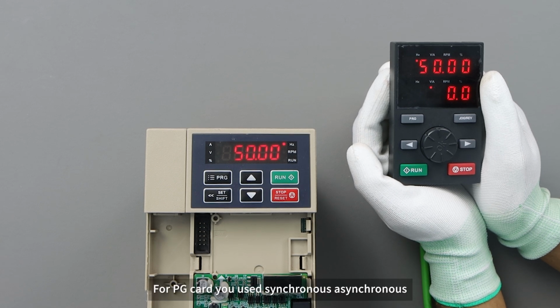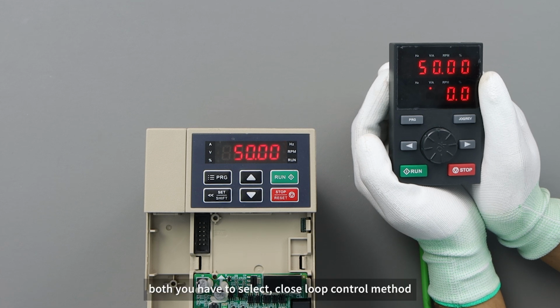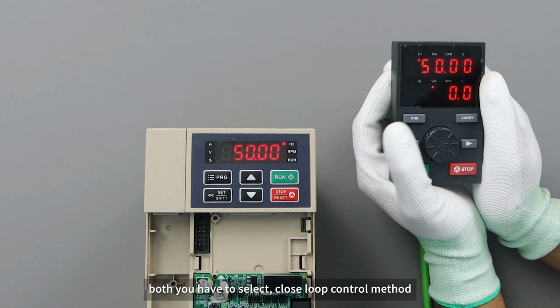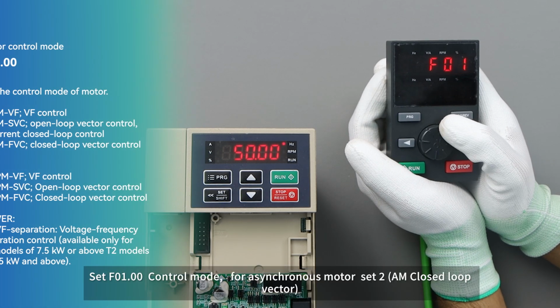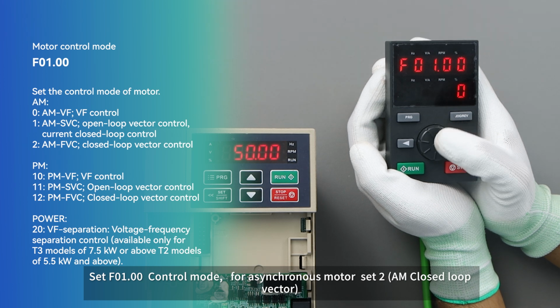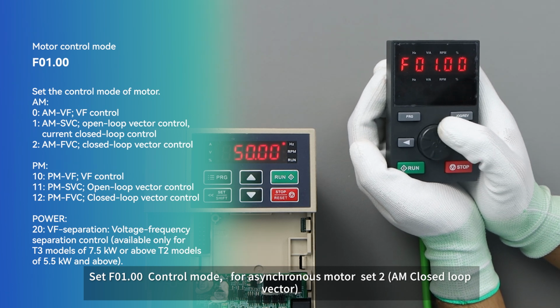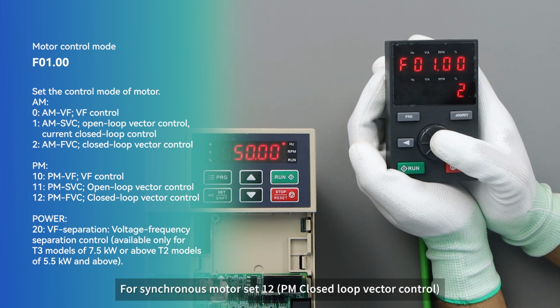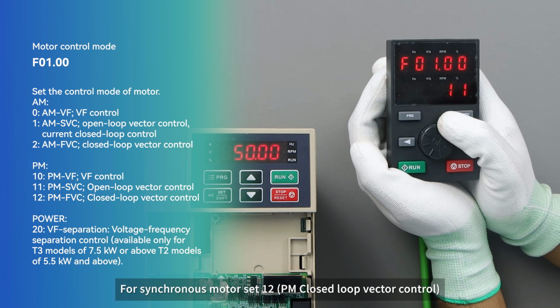For PG card, if your motor is synchronous or asynchronous, both you have to select closed loop control method. Set F01.00 control mode. For asynchronous motor, set 2. For synchronous motor, set 12.